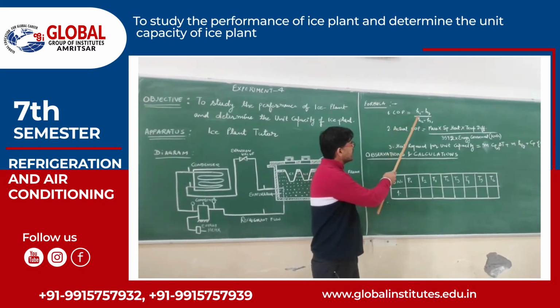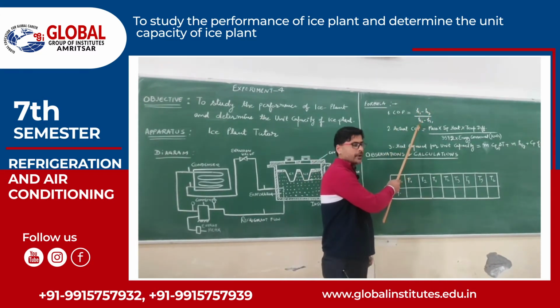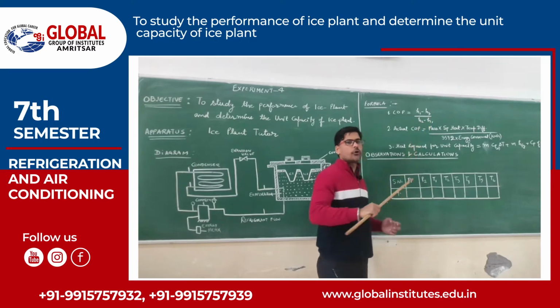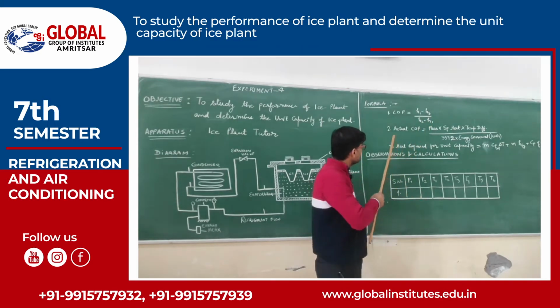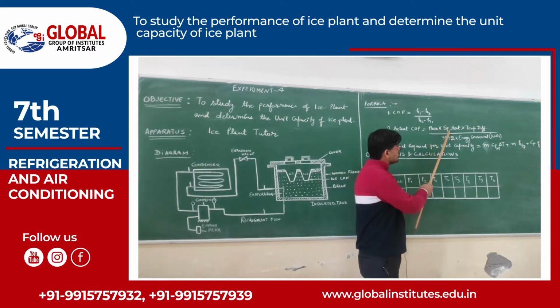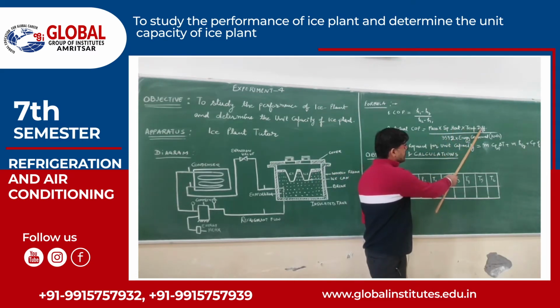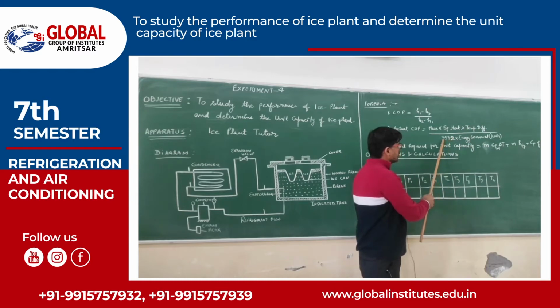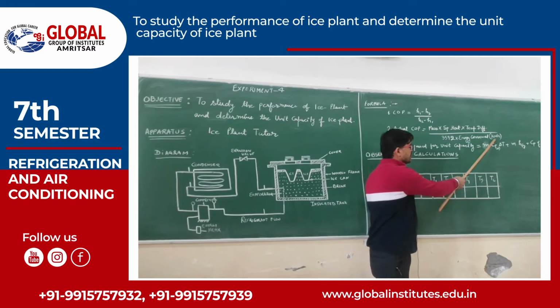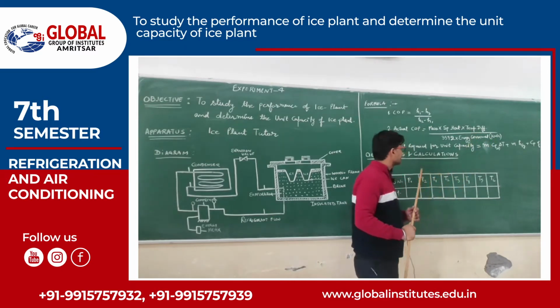Now move to the formulas which we have used in this experiment. The first is the coefficient of performance of the system, that is refrigeration effect upon work input, which we have already derived in the classroom. The second is the actual COP of the system: mass into specific heat into temperature difference upon 3592 into energy consumption by the compressor in kilowatt hour.